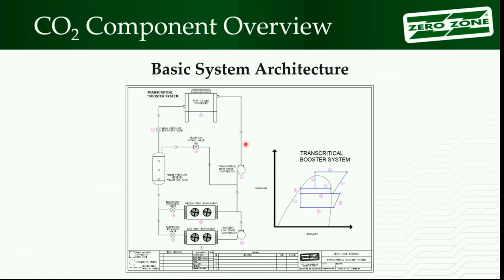Where does it start and where does it go to? It doesn't show you any elevations necessarily. A lot of times the condenser's drawn on the top of the piece of paper because it kind of looks right there. But there's no elevation. It's not showing you it's 20 feet up or 15 feet up or whatever else. It's really point-to-point connections on there. So we draw the components we talked about. You have a high-stage compressor, and I usually start with the compressors. On complex drawings, I can find them, and then I follow the lines around from there to hit the other components, see what's in the system.